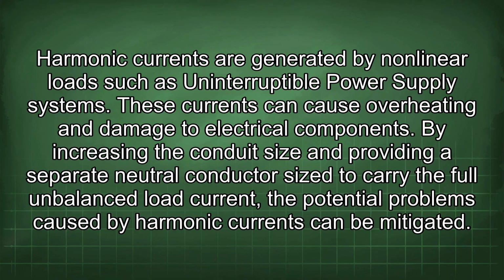Harmonic currents are generated by nonlinear loads such as uninterruptible power supply systems. These currents can cause overheating and damage to electrical components. By increasing the conduit size and providing a separate neutral conductor size to carry the full unbalanced load current, the potential problems caused by harmonic currents can be mitigated.